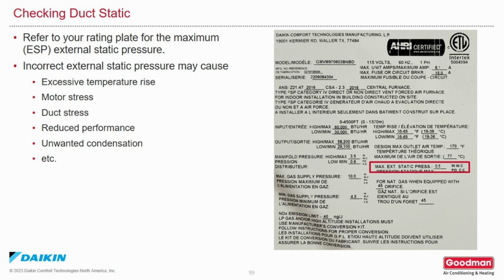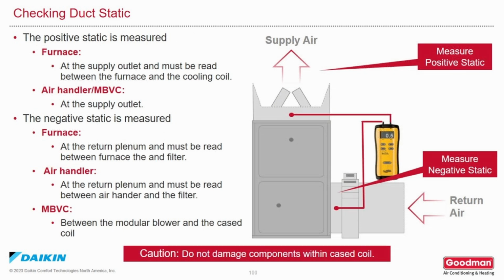It is important to check duct static pressure. Refer to the rating plate for the maximum external static pressure. Incorrect static pressure can cause excessive temperature rise, motor stress, duct stress, reduced performance, unwanted condensation by blowing water off of the coil, etc. For checking duct static pressure, positive pressure is measured on a furnace at the supply outlet and must be read between the furnace and the cooling coil.